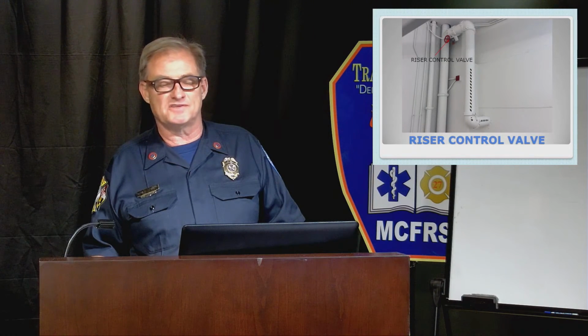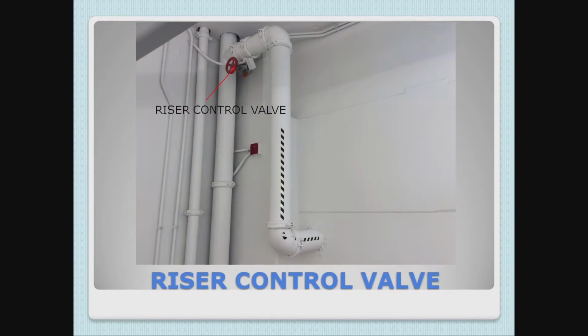The way that valve is designed, there's a spring that controls the pressure. It's going to basically see high pressure on the supply side of the valve, and it's going to shut itself down, assuming it has plenty of pressure. This building did not have pressure reducing fire hose valves. So you would have had the opportunity to isolate the standpipe and pump into the system through one or two fire hose valves.